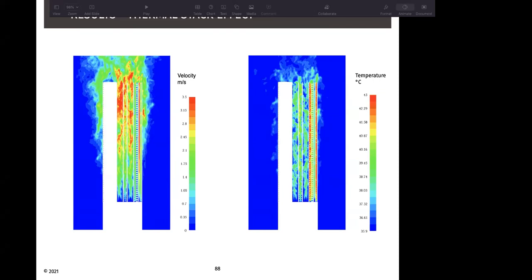And on the right hand side, you can see the temperature for the same. So within the shaft, there is an increase in temperature, and it is rising, and it is affecting the ODUs in the floors which are above it. So for a lower level, you would see that the thermal stacking is not as much, because it's starting at the lower level.